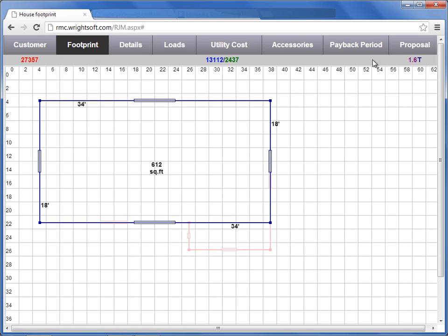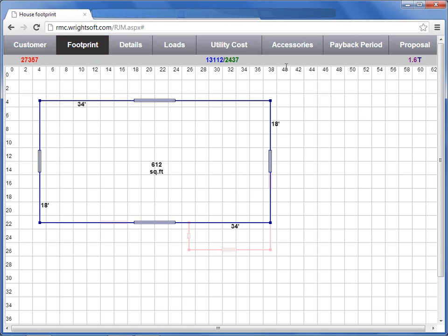On the far right hand side is your tonnage. As discussed earlier, the sensible heat ratio will change your target tonnage. The higher your sensible heat ratio of your equipment, the lower your tonnage will be. The lower your sensible heat ratio of your equipment, the higher your tonnage will be. Remember, the sensible load is divided by the sensible heat ratio to determine your target tonnage.